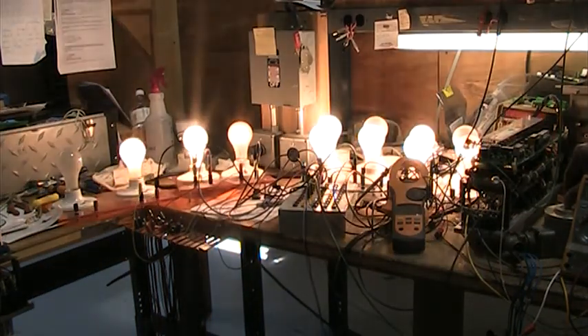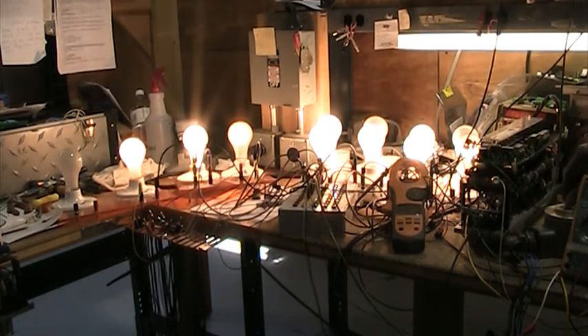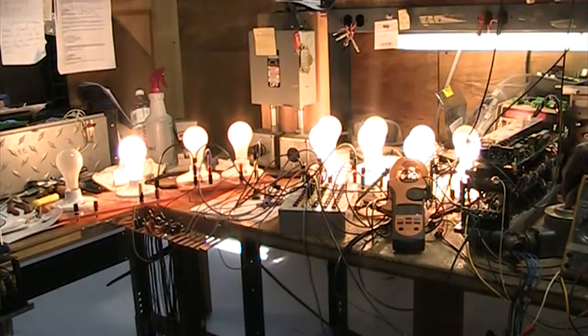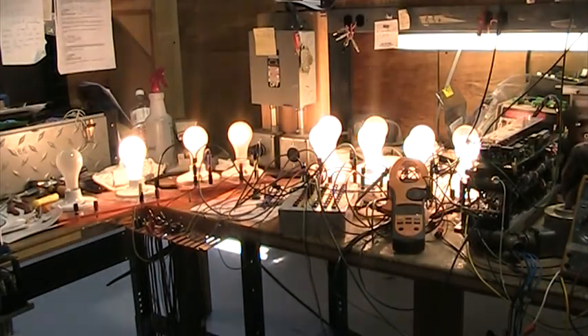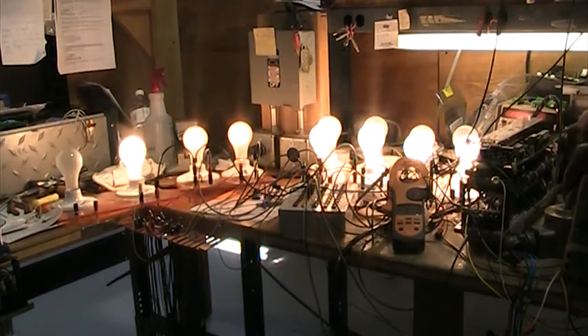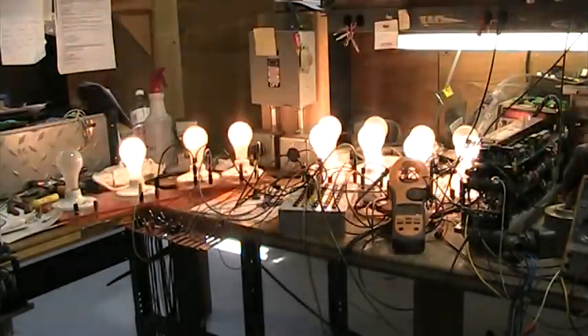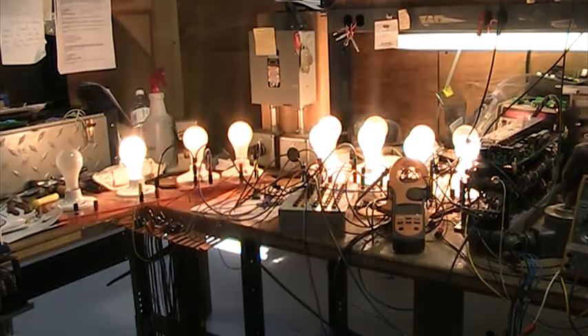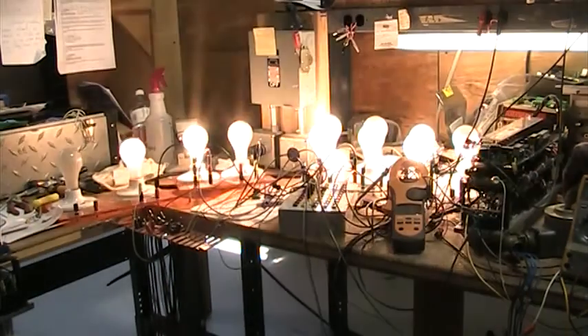We are phasing all the outputs and the bus current is constant. Not dropping. No faults. Things seem to be working real smooth.